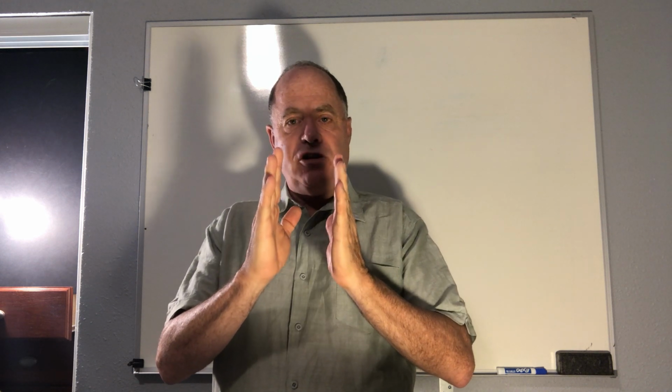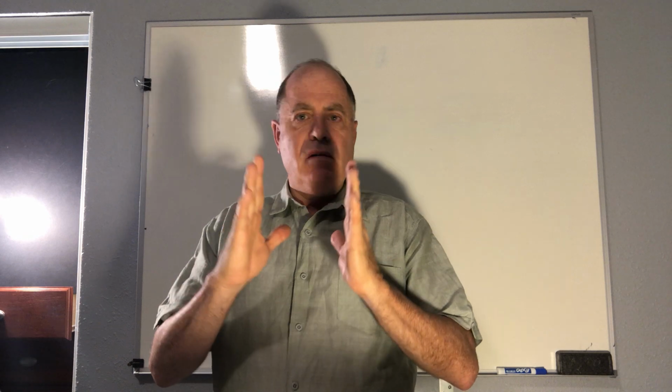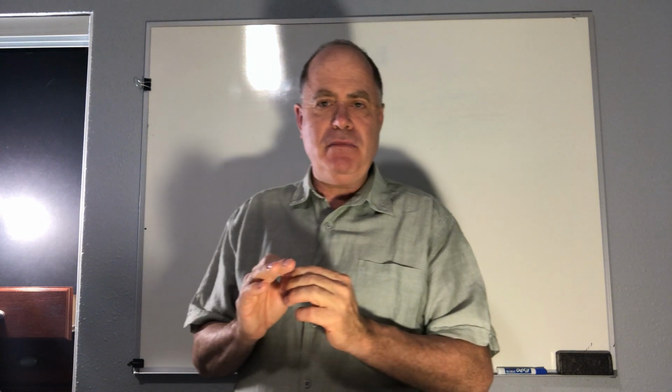Let's talk about vibration isolators. A lot of times we have vibration isolators, and years ago they're connecting to ductwork, right? And I just mentioned canvas again here with the vibration isolators. In the 1950s, 60s, and 70s, they actually were made of canvas, and then they tend to be made of a kind of rubber material, polyethylene, that was flexible. And that allowed, when you connected the ducts together, a little bit of leeway or play, so the alignment didn't have to be exactly perfect to the millimeter.